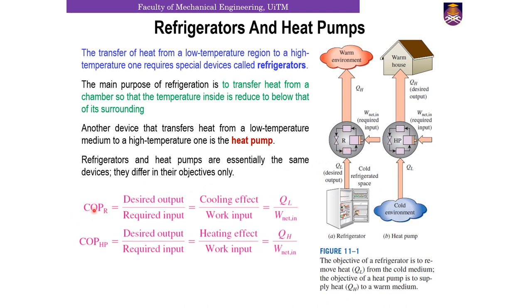Now, why we use coefficient of performance and not efficiency is because in a refrigeration cycle, your desired output can be more than your required input. As a result of that, your COP can be more than unity, so it can be more than one. So in order to avoid the confusion, instead of using efficiency, we use the term coefficient of performance here.